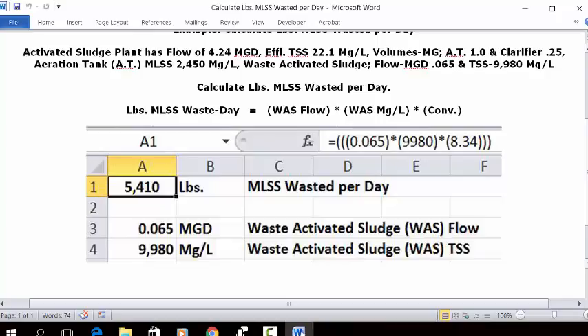Enter: equal sign, three open parentheses, 0.065, close parentheses, multiplication key, open parentheses, 9980, close parentheses, multiplication key, open parentheses, 8.34, close parentheses, and press Enter. In A1 your answer is 5,410 pounds of MLSS wasted per day.